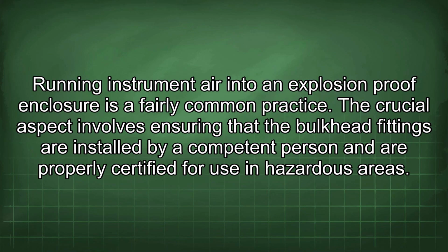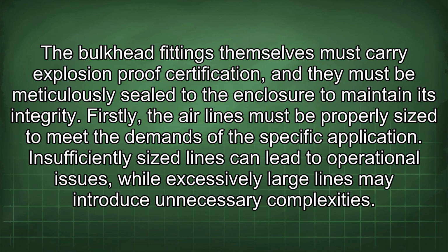Running instrument air into an explosion-proof enclosure is a fairly common practice. The crucial aspect involves ensuring that the bulkhead fittings are installed by a competent person and are properly certified for use in hazardous areas. The bulkhead fittings themselves must carry explosion-proof certification, and they must be meticulously sealed to the enclosure to maintain its integrity.